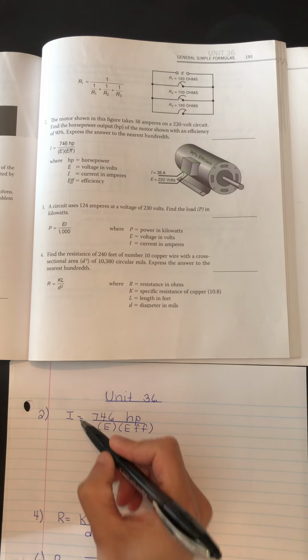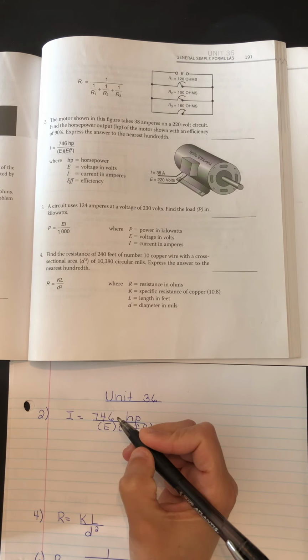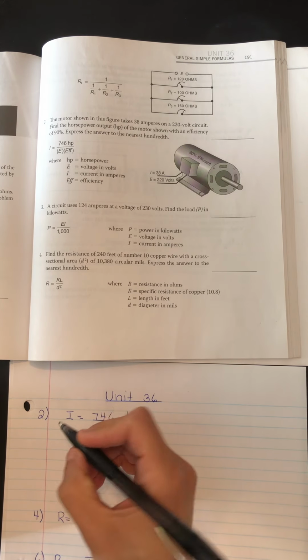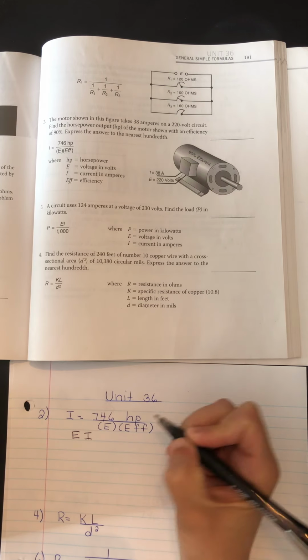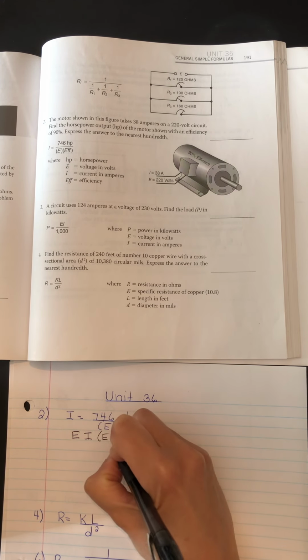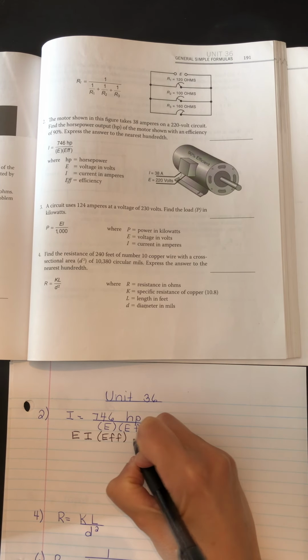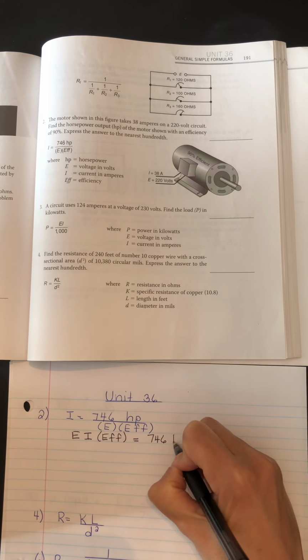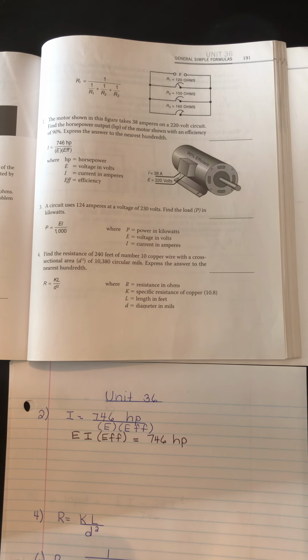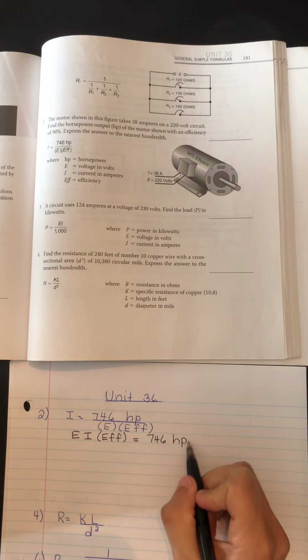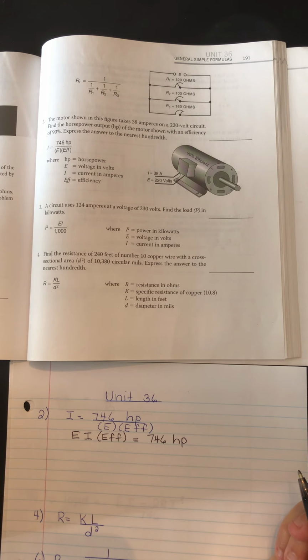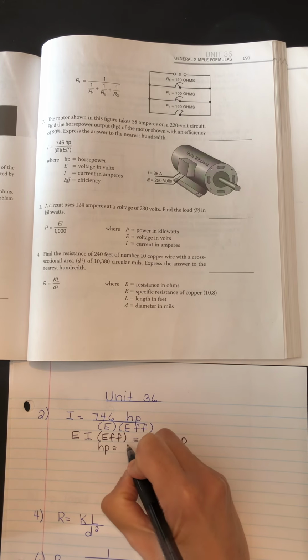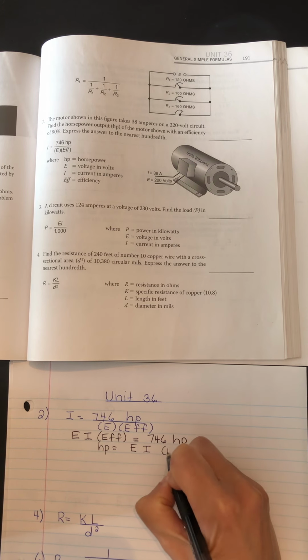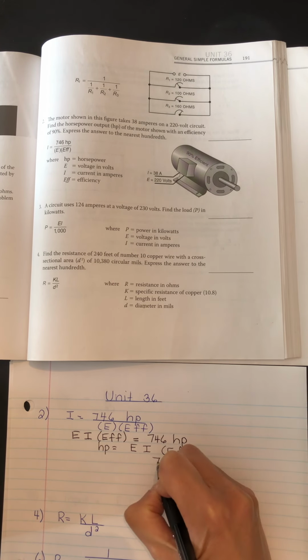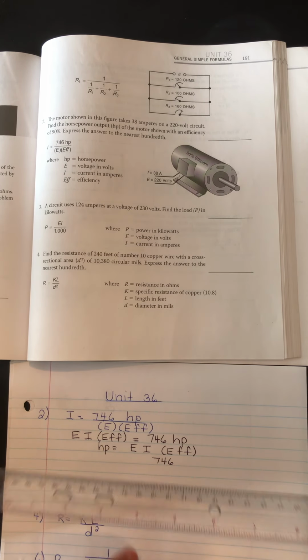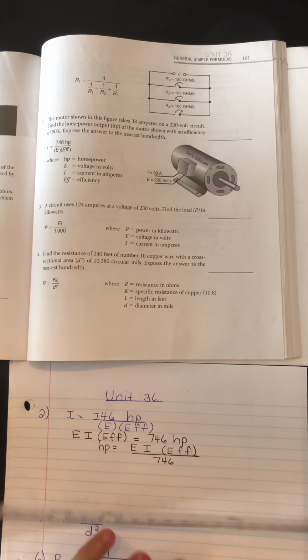In order to isolate HP, we can start by doing that cross multiplication. So then of course we get the fact that E times I times the efficiency is equal to 746 multiplied by the horsepower. So now, in order to isolate HP, we would simply divide by 746. So we're going to get the following. We're going to get E times I times the efficiency divided by 746 will give us the power output in horsepower.